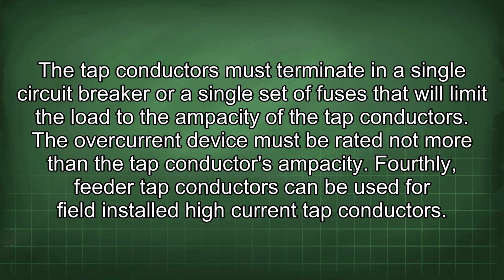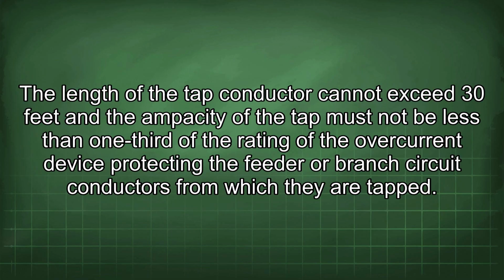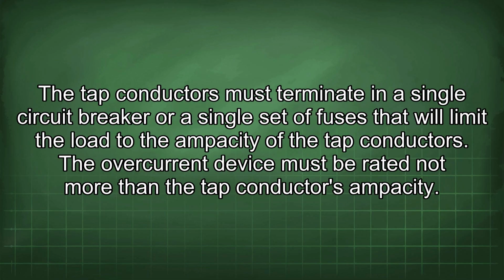Fourthly, feeder tap conductors can be used for field-installed high-current tap conductors. The length of the tap conductor cannot exceed 30 feet and the ampacity of the tap must not be less than 1/3 of the rating of the overcurrent device protecting the feeder or branch circuit conductors from which they are tapped. The tap conductors must terminate in a single circuit breaker or a single set of fuses that will limit the load to the ampacity of the tap conductors. The overcurrent device must be rated not more than the tap conductor's ampacity.